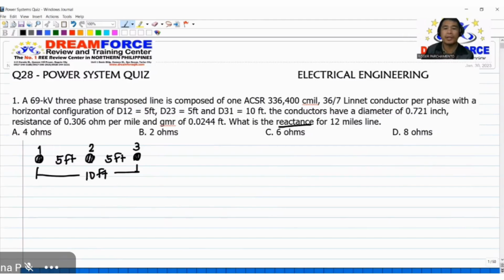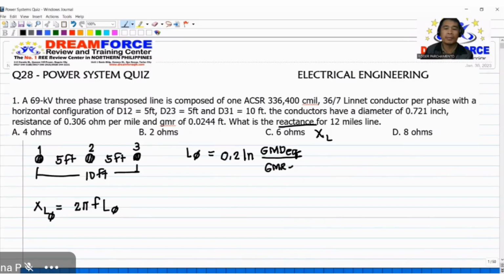Okay, so what is the reactance? It is asking for XL. So XL for 3 phase is equivalent to XL per phase. We have 2 pi times the frequency times the inductance per phase. So wherein the inductance per phase is equivalent to 0.2 times ln of the GMD equivalent all over the GMR equivalent. This is in millihenry per kilometer.